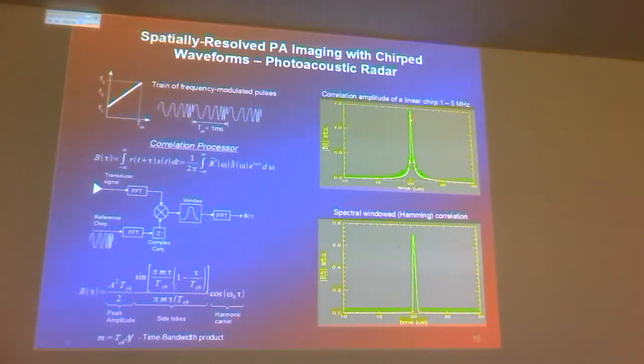And you have a correlation for a chirp of 1 to 5 megahertz here. This is the function that you're looking at. And the most important thing is this one, this M, the time bandwidth product. That time bandwidth says, how long has the chirp lasted? The longer it lasts, the more energy it puts in, and so the stronger your signal-to-noise ratio is going to be. And how about the bandwidth? The higher the bandwidth that it covers, the narrower the half-width will be.